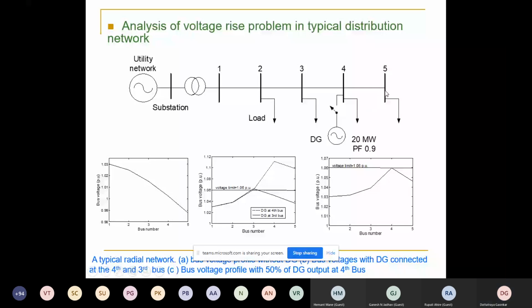Suppose it's an 11 kV feeder. The operator sitting at the substation level has to ensure voltage is maintained constant throughout the network. But that's not going to happen because of the physical parameters of the network—voltage keeps dropping, depending on several factors. So the last customer may not see the proper voltage level; his light may come to full brightness only at night. That's why I'm talking about a long rural feeder—these issues still exist. So voltage keeps dropping from the substation to the customer, depending on several parameters.